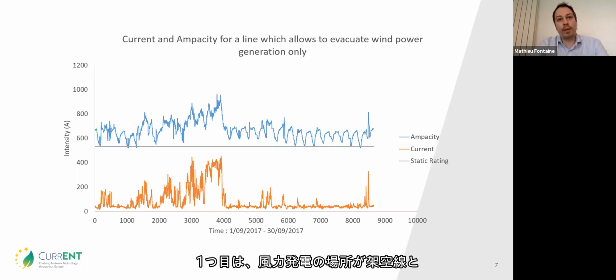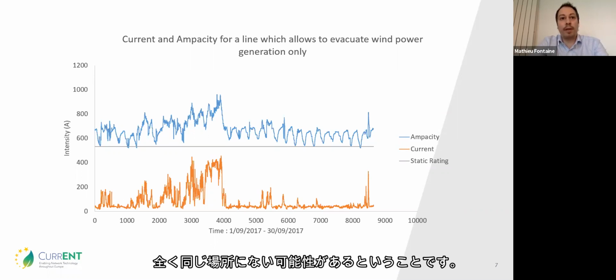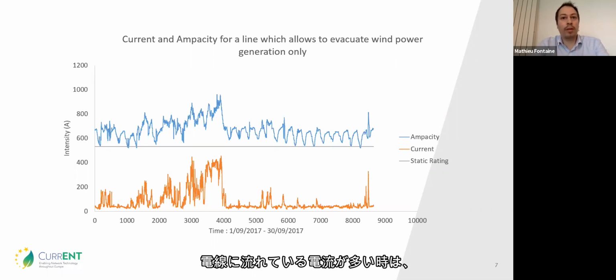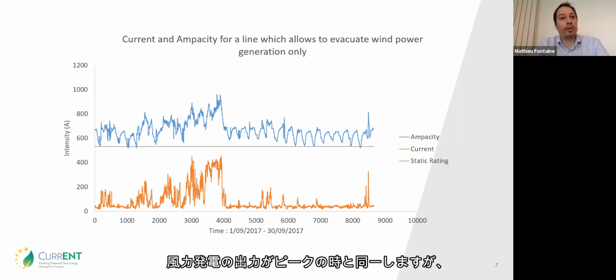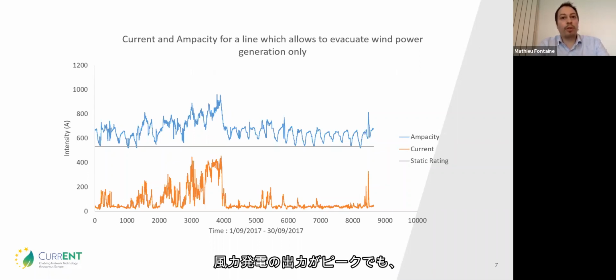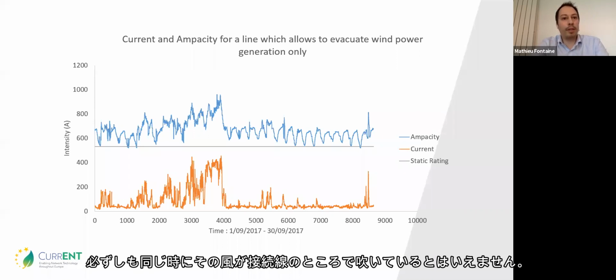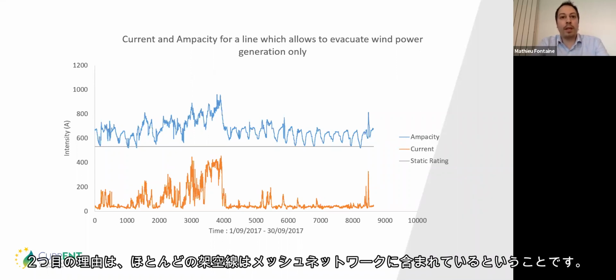The first reason is that wind turbines may not be located exactly at the same place as the overhead line. Times when line currents are very high coincide with periods when wind power generation is at its peak, but even then it doesn't necessarily mean that wind is blowing on the conductor.